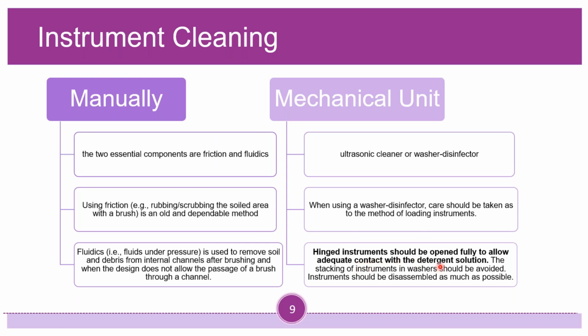So hinged instruments should be opened fully to allow adequate contact with the detergent solution. The stacking of instruments in washers should be avoided. Instruments should be disassembled as much as possible. Your hinged instruments, everything needs to be open, so that when they're in the washer disinfector, it can get into all those nooks and crannies and crevices and clean everything out real good.